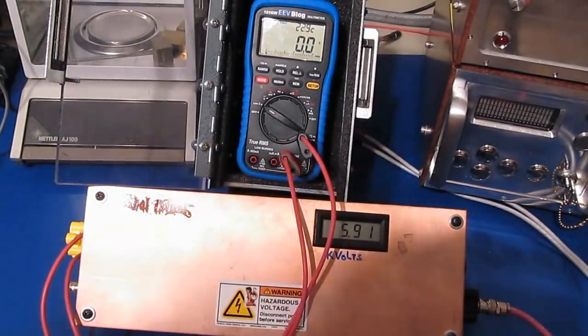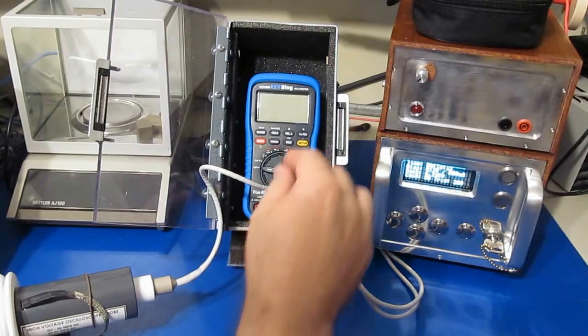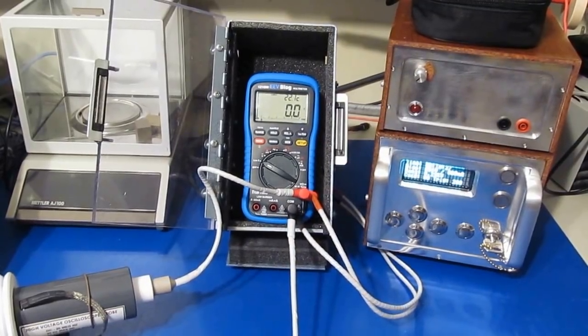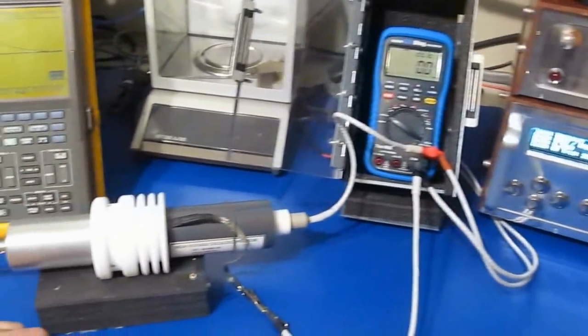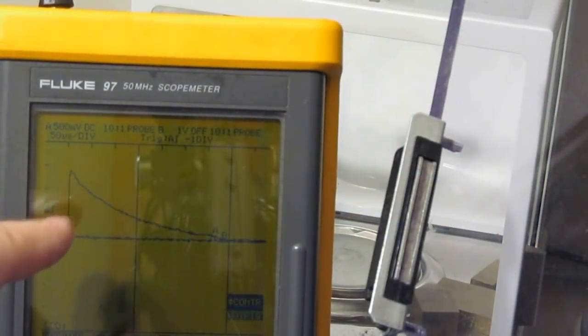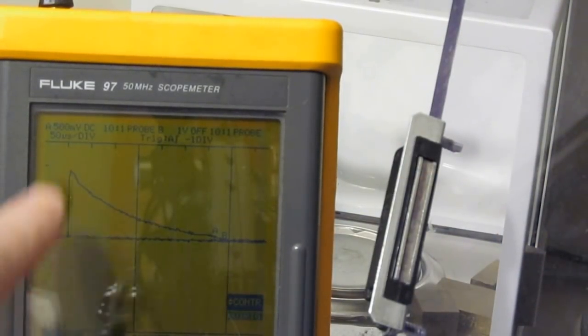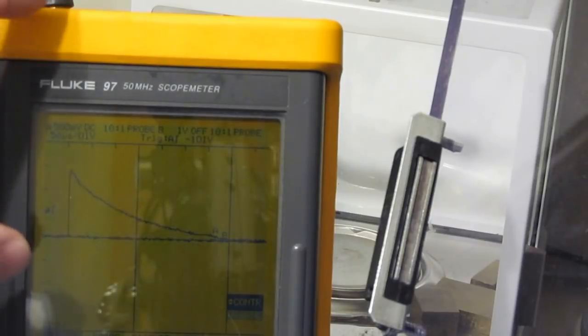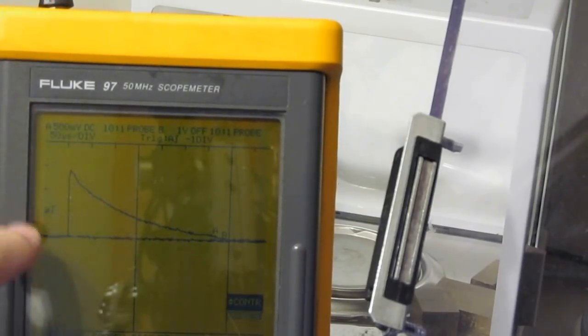Alright, I'll go ahead and functional test it. So the 121 survived the ESD testing just fine. So I've got our high voltage probe out. You can see I have it attached to our Fluke 97 right now. This is currently set for 500 volts per division. And you can see we're 3 divisions up.